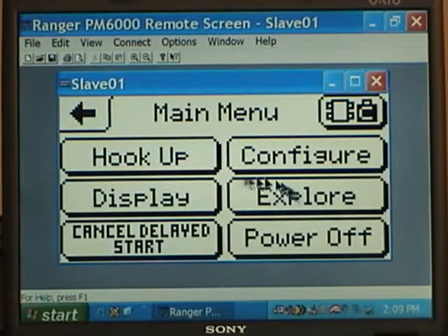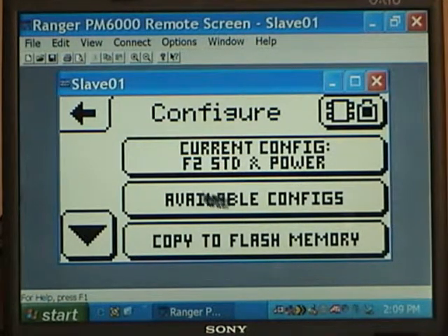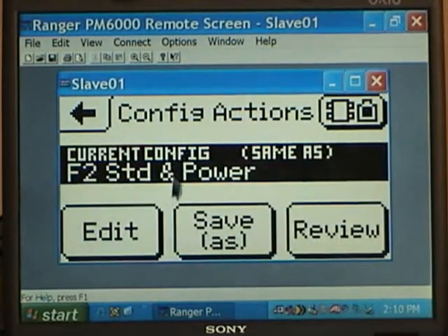Then we have the configure key. When we push the configure key, you would be able to see what the current configuration is. Remember, there's 8 different ones, or what the available configurations are. And in this case, we can look at the current configuration, and we see that the current configuration is configuration number 2, which is your standard 3 voltages and 2 currents. Remember, we do measure L1 to L2, so it's 3 voltages with our unit. And power, watts, vars, power factor, VA.